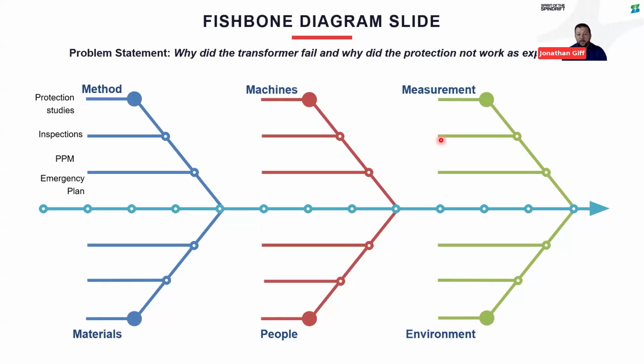Building on what Cody said as well, when you're looking at your maintenance plans, does protection form part of that? Dan had mentioned that these are old electromechanical relays, so you would ensure that these form part of your preventative maintenance, that the mechanical disc is being proven as part of your maintenance, because these can seize, as any mechanical device can do. But yeah, protection studies is a good starting point.